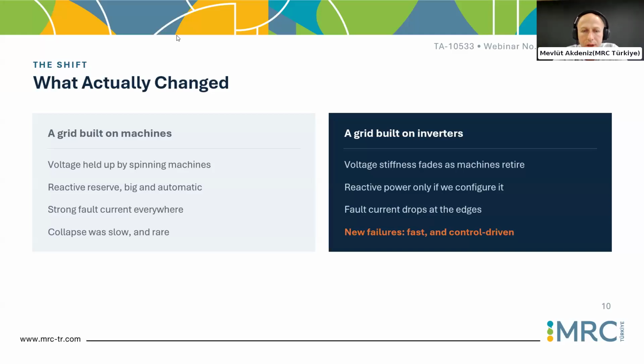let's say, because in the past, as we were using conventional generators in our grids, mainly hydraulic power plants or thermal power plants, let's say rotating machines, they are all synchronous generators, and they also provide the reactive reserve. They have large reactive reserves.